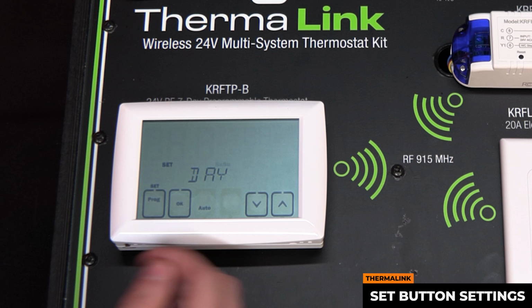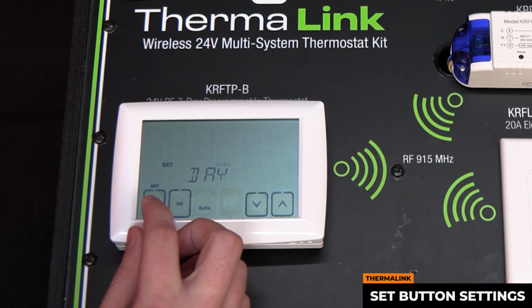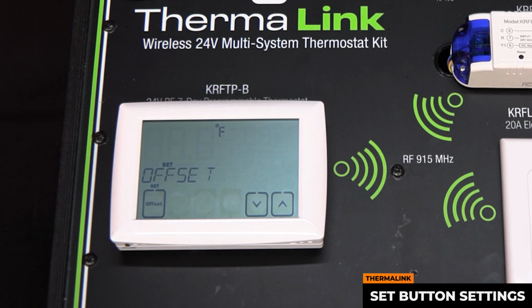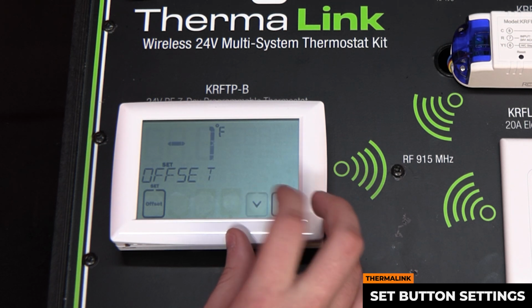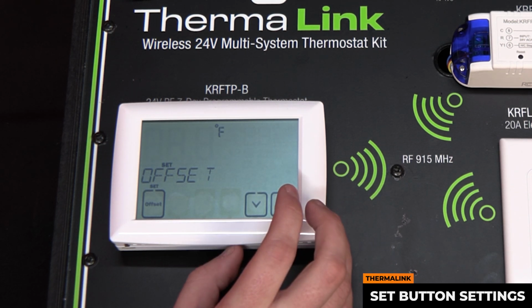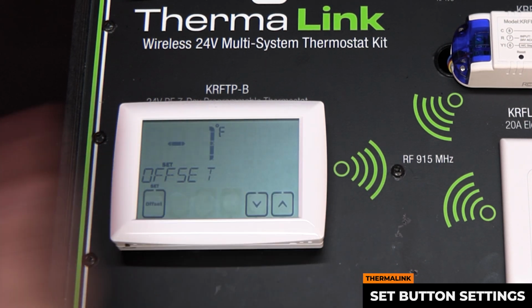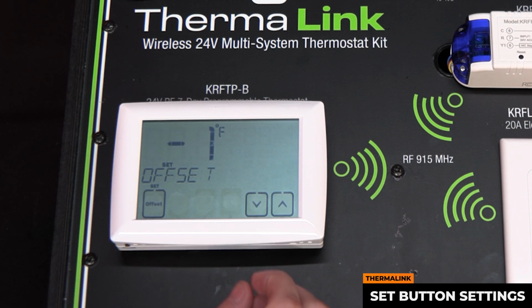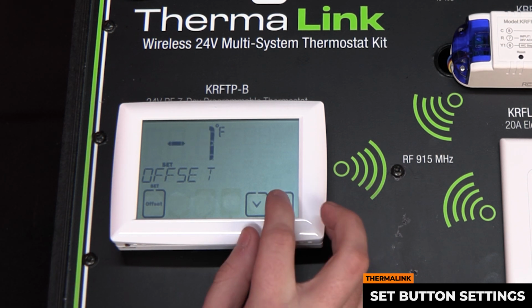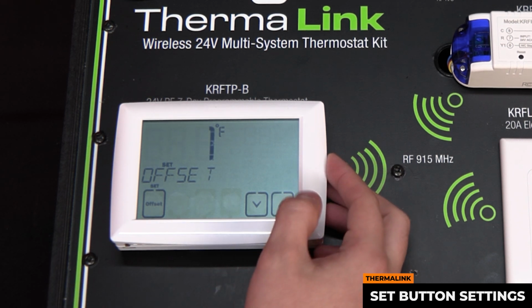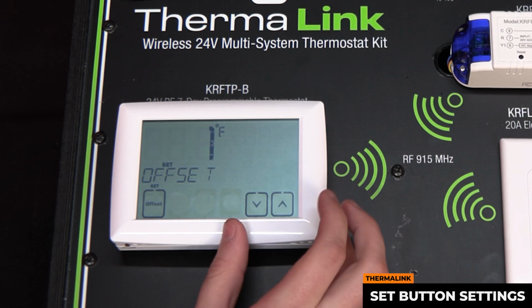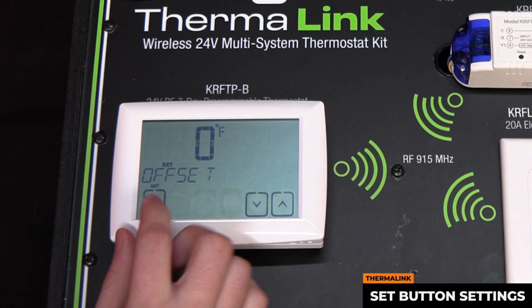And once you are done programming your schedule, you can hit set again. So now it's going to ask for the offset. So this should be used if the temperature that's being displayed is slightly higher or lower. So say you're reading a little bit higher than it should be, you'll offset it by -1 degree Fahrenheit. Or if you want to read a little higher, you can go up to 1. There's only a -1 to 1 offset you can have. You'll program that.